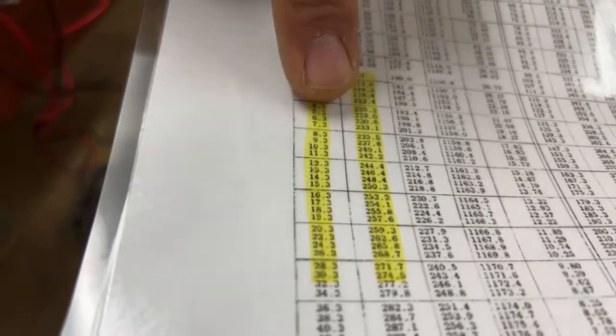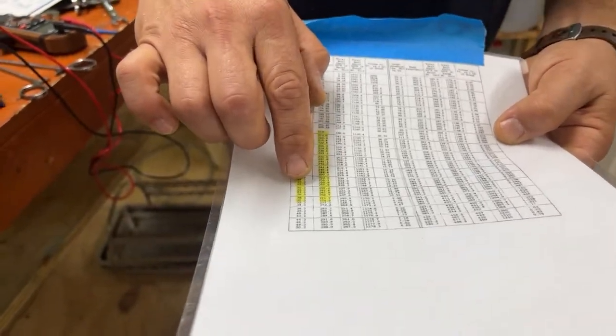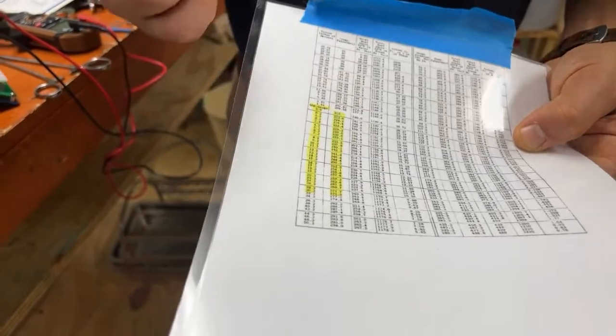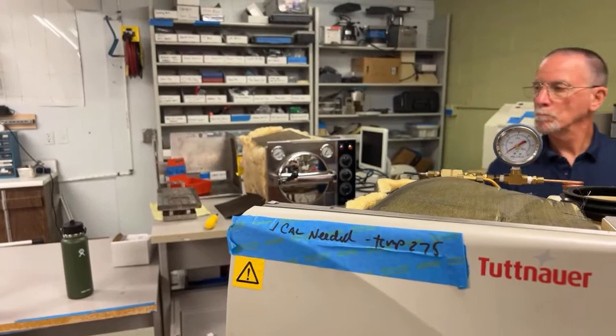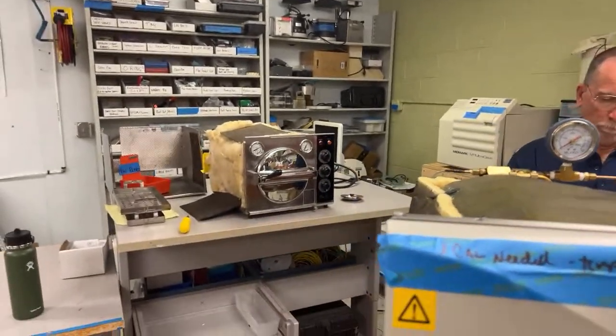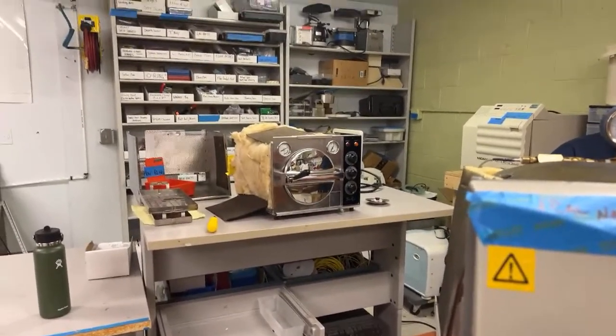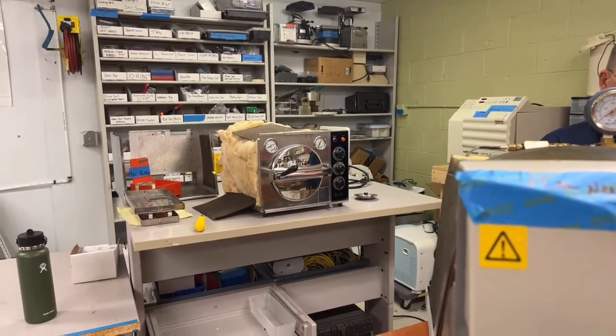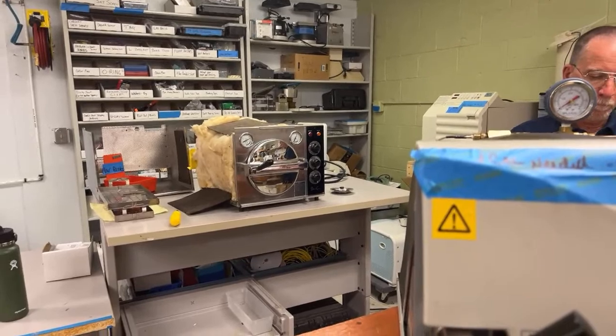Most problems with an autoclave are going to result from some sort of a steam leak. As you can see here, at 212, we're at 0. But then as we start clocking up to 222, we're at 3.3, and 233, 7.3. So this is a really cool correlation between pressure and temperature. Say you have a unit where maybe the pressure gauge, like the one right over here, this Pelton Crane unit, is only achieving 250, or 260 degrees. One of the questions we have to ask ourselves is, is it an indication problem, or is the unit actually not achieving temperature and pressure? This is where the correlation comes in.